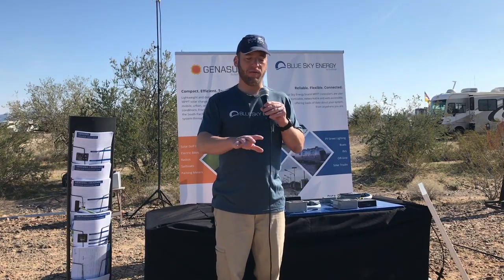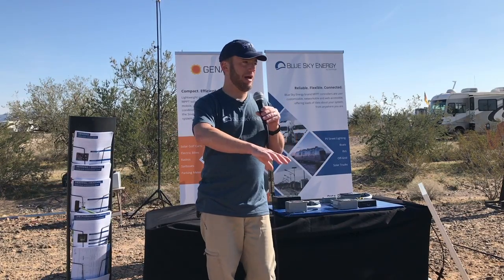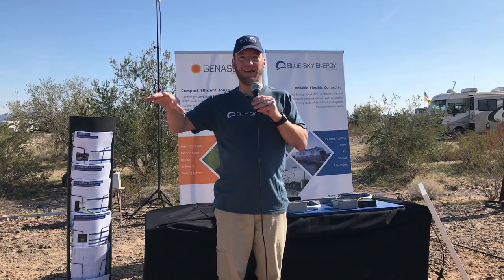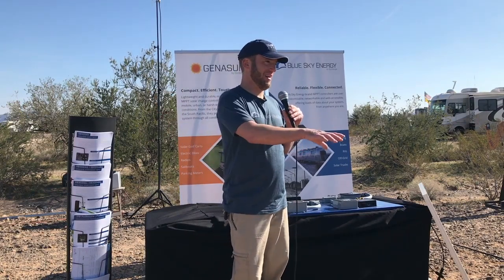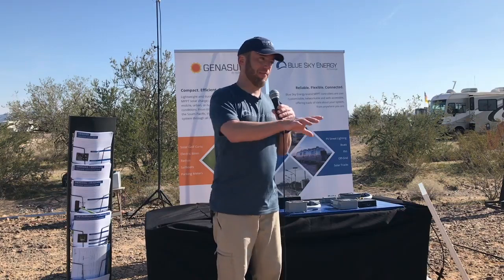When you combine different panels, we talked a bit before about series versus parallel. When you combine panels in parallel, you have to make sure their output voltage, their VMP, is ideally within 0.5 volts of each other. Just like if you shade one panel and drag it down, you don't want a panel with a VMP of 19 connected to one with a VMP of 18, because the 19 will come down to about 18. You can match different wattage panels in parallel—this one could be 150 watts and that one 50 watts—as long as the VMP is within about 0.5 volts of each other.